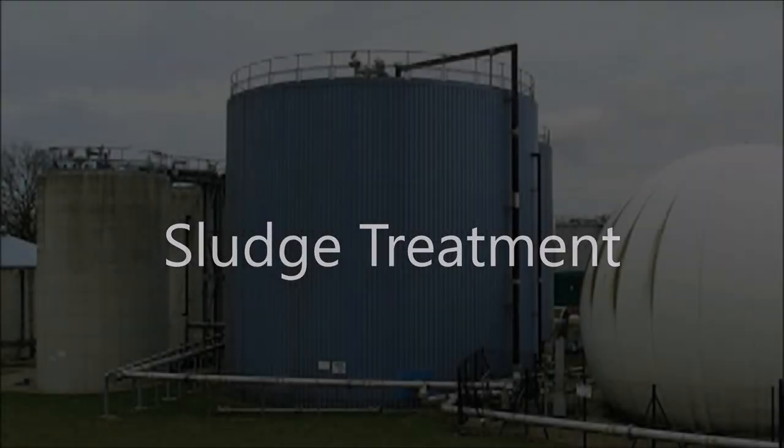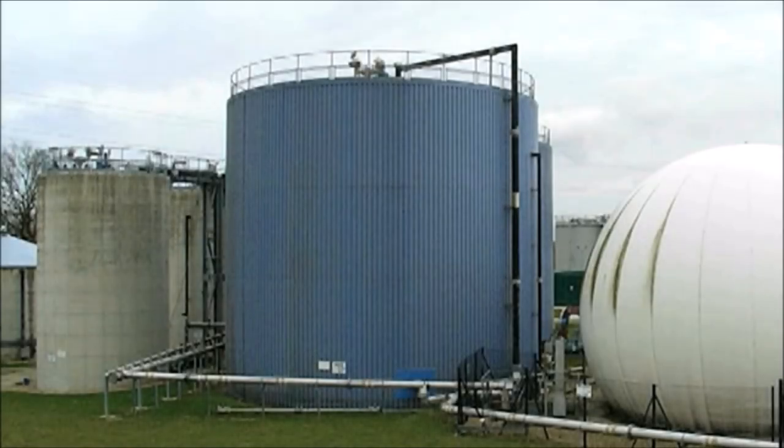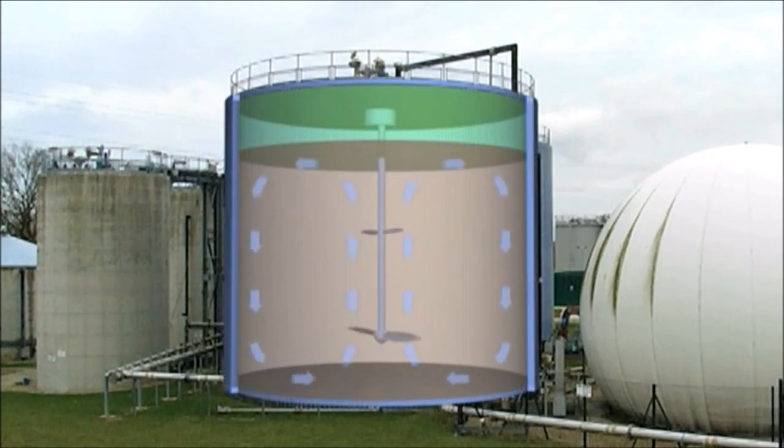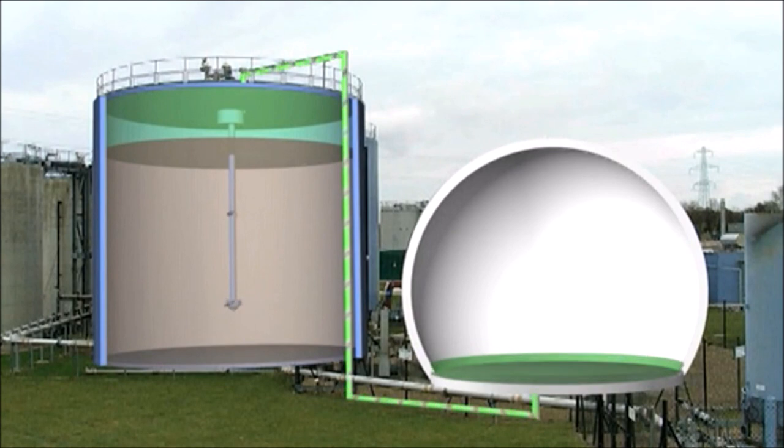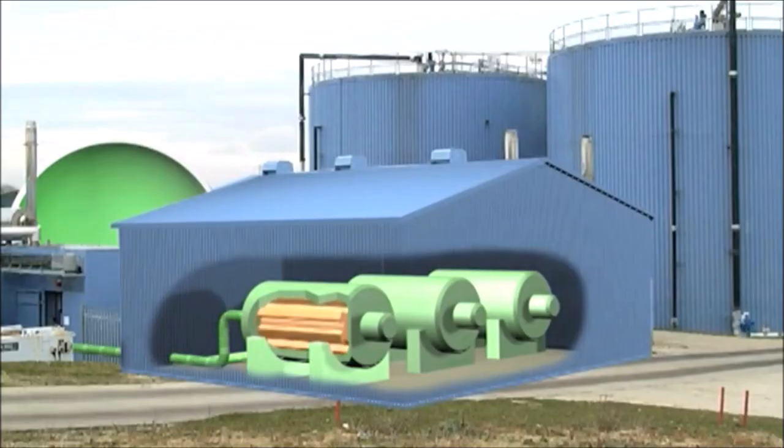The sludge from the settlement stages is pumped into the digester tanks. The temperature in the tanks is kept at around 35 degrees Celsius. The bacteria, which have no oxygen, slowly break down the sludge. This process produces methane gas, which can be drawn off and stored in this gas balloon, before being used to generate electricity in a combined heat and power plant.